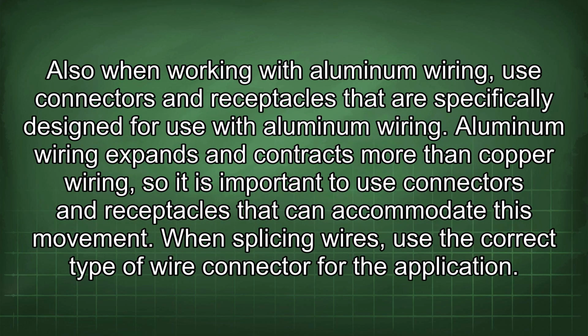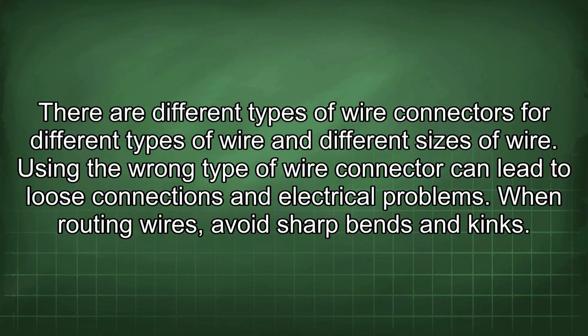Also, when working with aluminum wiring, use connectors and receptacles that are specifically designed for use with aluminum wiring. Aluminum wiring expands and contracts more than copper wiring, so it is important to use connectors and receptacles that can accommodate this movement. When splicing wires, use the correct type of wire connector for the application. There are different types of wire connectors for different types of wire and different sizes of wire. Using the wrong type of wire connector can lead to loose connections and electrical problems.